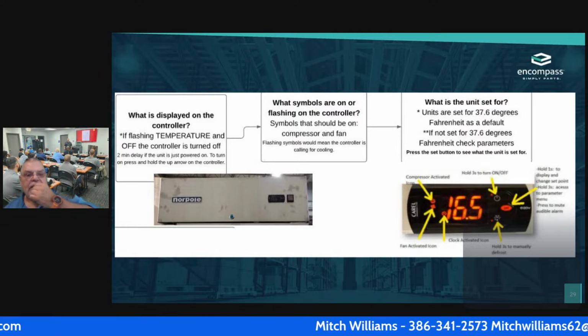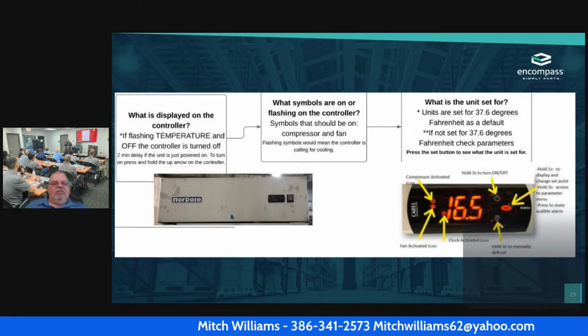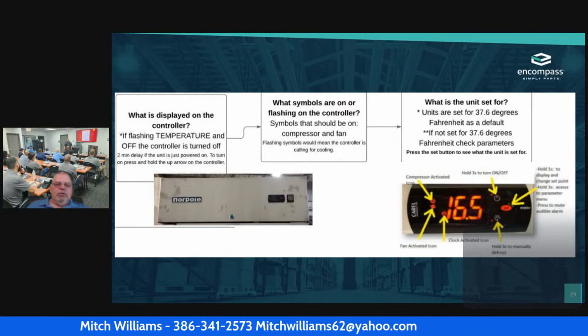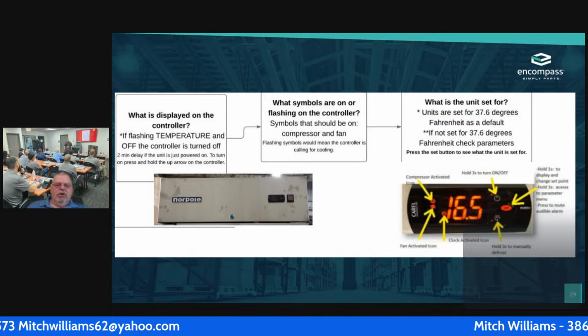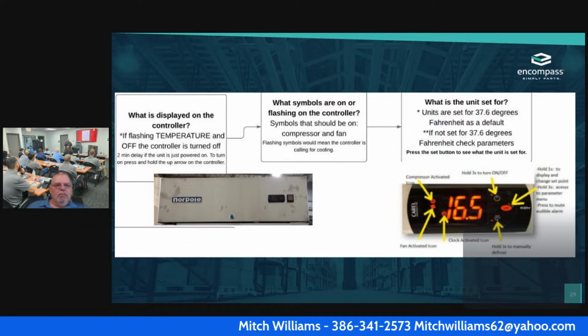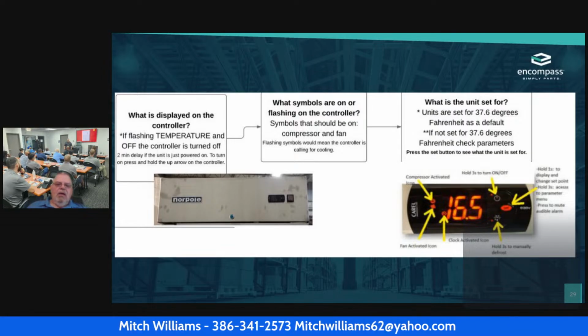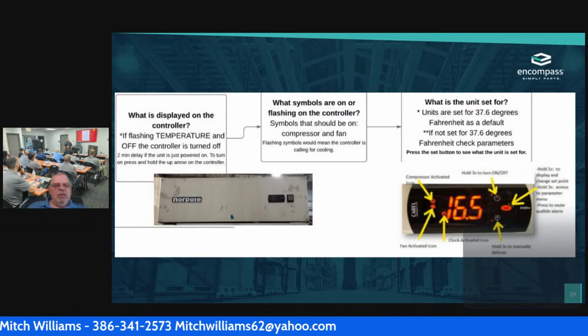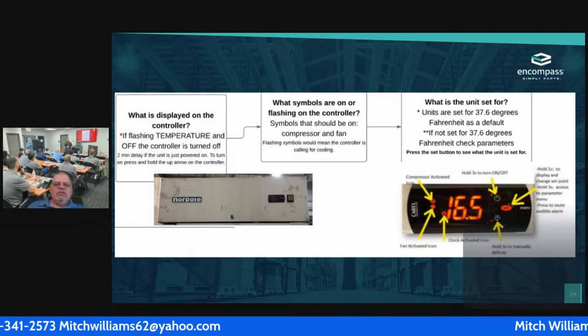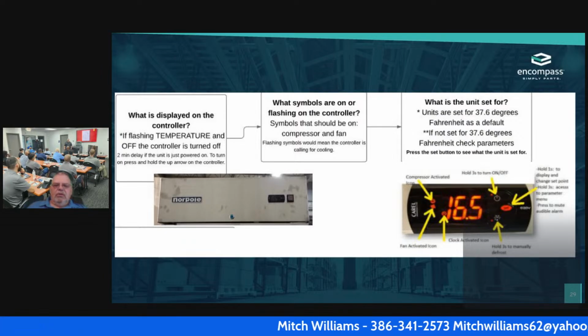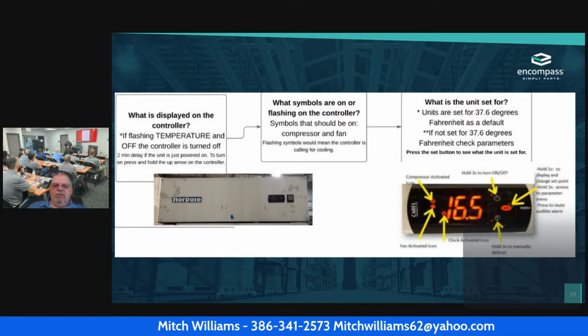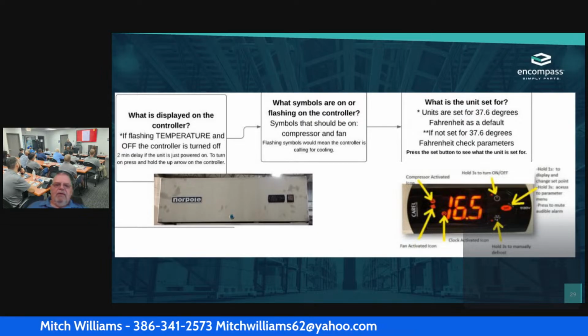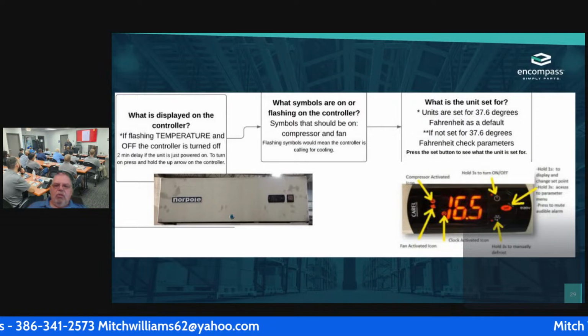So here we are again. What's in the display? If the display is flashing the temperature and off on the controller is turned, the unit's turned off. Okay. 2 minute delay. This is for you to remember. There's a 2 minute delay for it to start up, so it's not going to immediately start up. Okay. What symbols are on the flashing controller? The symbols that should be on are the compressor and the fan, the ones that are on the far left. Okay. Flashing symbols would mean that the controller is calling for cooling.